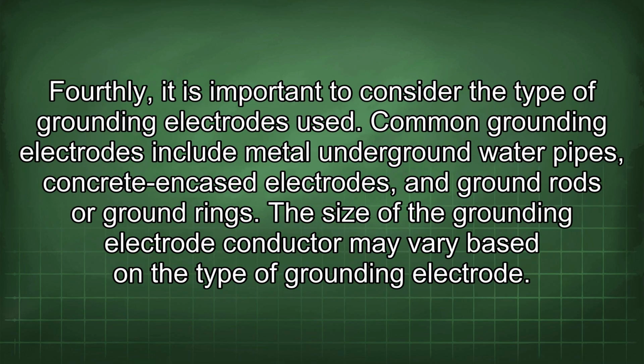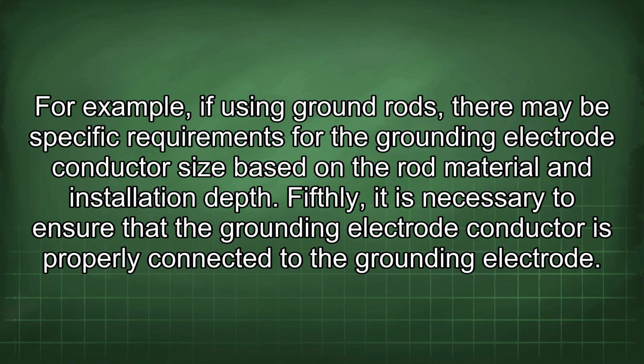Fourthly, it is important to consider the type of grounding electrodes used. Common grounding electrodes include metal underground water pipes, concrete encased electrodes, and ground rods or ground rings. The size of the grounding electrode conductor may vary based on the type of grounding electrode. For example, if using ground rods, there may be specific requirements for the grounding electrode conductor size based on the rod material and installation depth.